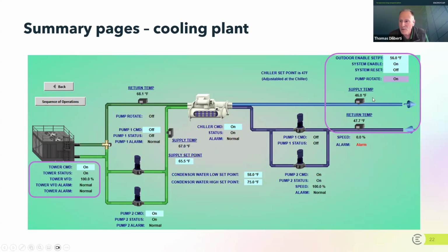We've got another enable set point up here of 56 degrees, which means that when we get above 56 degrees, the whole cooling plant is going to operate. And I also wanted to bring to your attention this idea of the pump rotate, this little purple box here. This is saying that these pumps now, these redundant pumps, this is another example of one. Again, one's on, one's off, which is good.